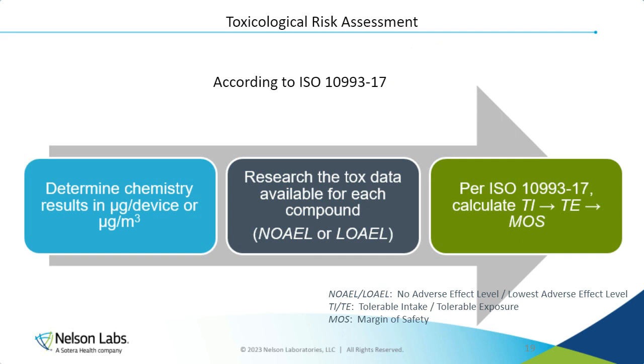The basic steps for a toxicological risk assessment are: generate your chemistry results from your medical device. This is done with that robust testing. Then research available toxicological data for each compound from literature reviews. Here we try to determine the NOAEL, the no observed adverse effect level, the LOAEL, the lowest observed adverse effect level, or any other relevant points of departure. These are then computed into a tolerable intake and a tolerable exposure, taking into account uncertainty factors throughout. And then it is further calculated into a margin of safety. These points of departure are researched through a literature review of trusted databases, such as PubMed, ECHA, ToxNet, ATSDR, and the IRIS database.